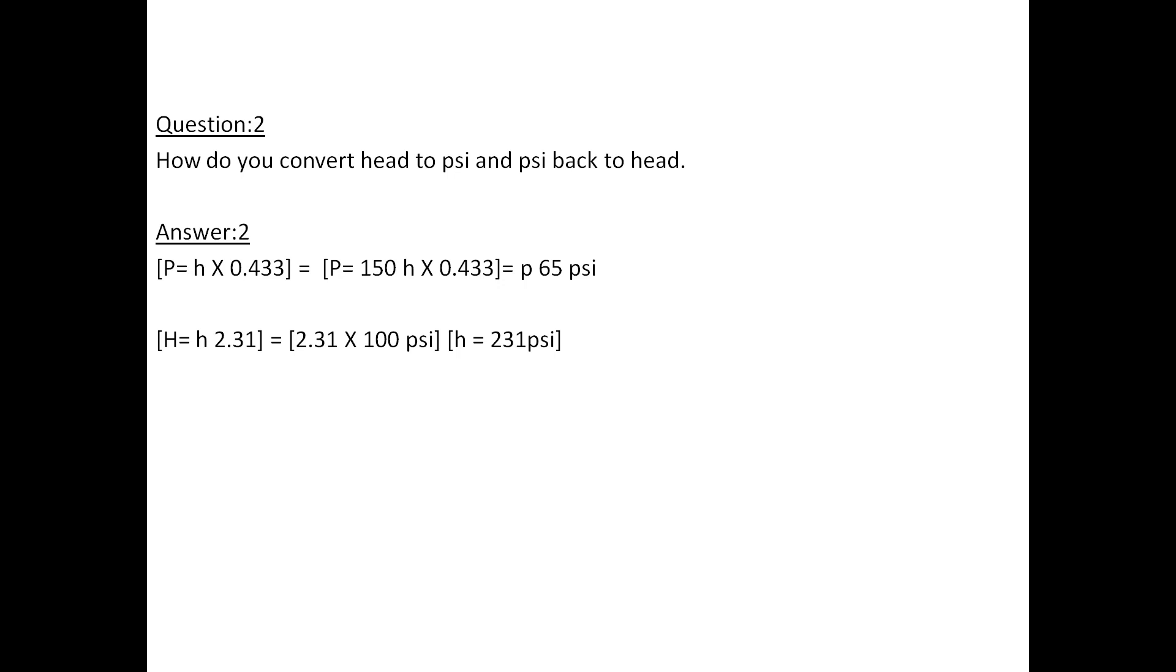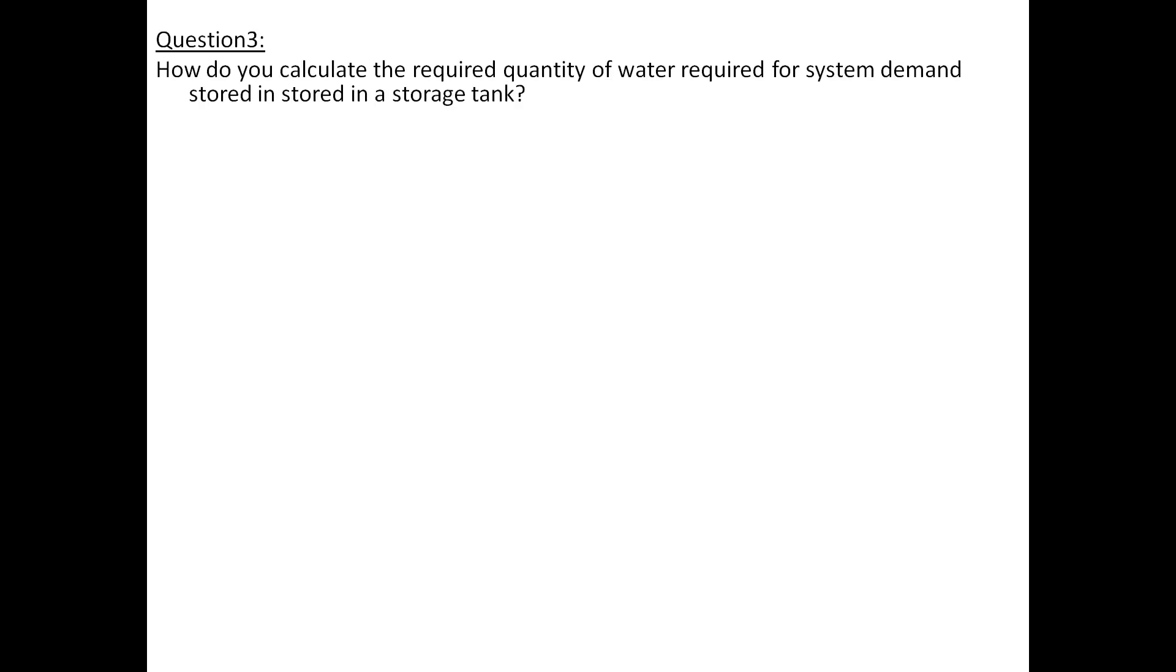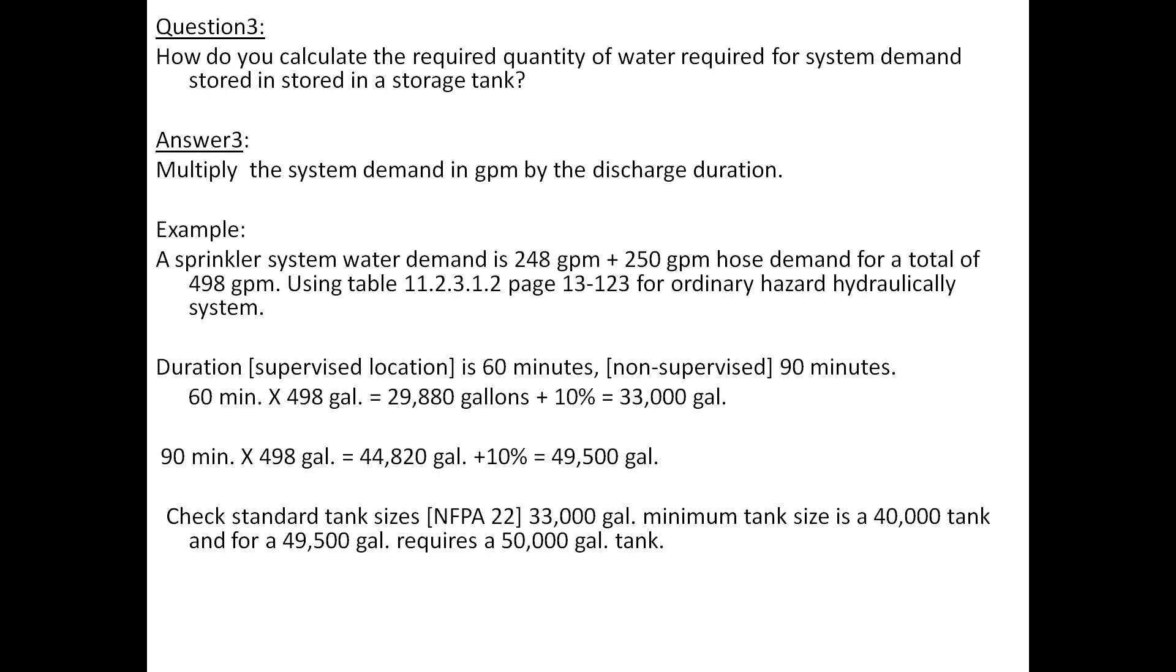Question number 3: How do you calculate the required quantity of water required for system demand stored in a storage tank? The answer to question number 3 is you multiply the system demand in gallons per minute by the discharge duration.